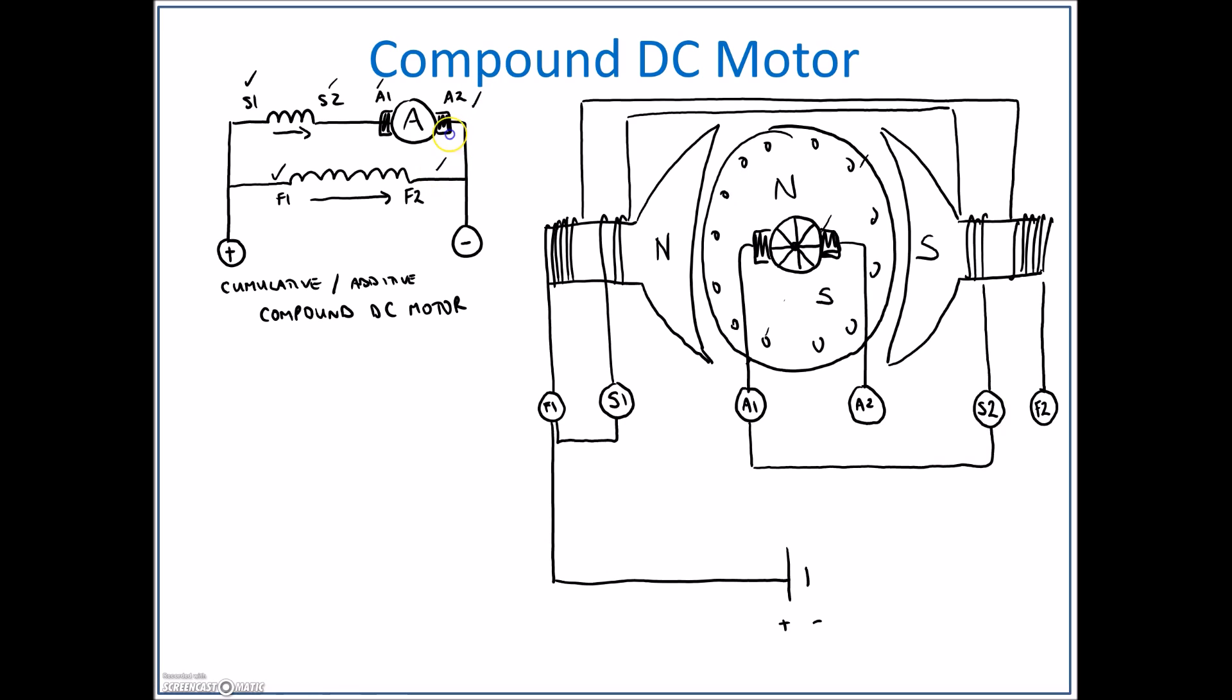And then A2 and F2 both reference the same polarity, and then we just need to bring our source polarity there. So I'm going to bring my other side of the source over to F2. So that corresponds from here to here, and I'm going to put a jumper over to my A2 connection. Beautiful. And that is all our connections for the cumulative compound DC motor.